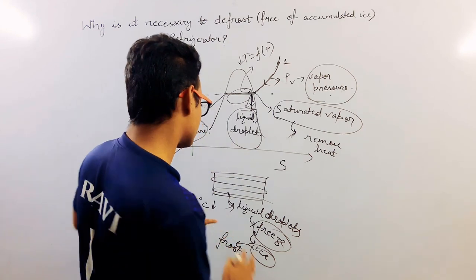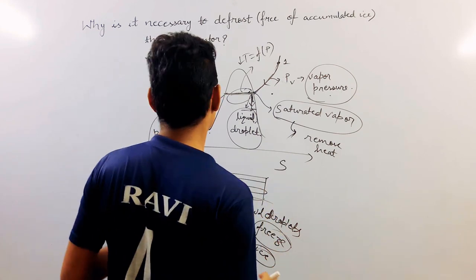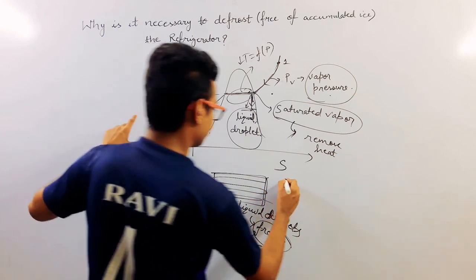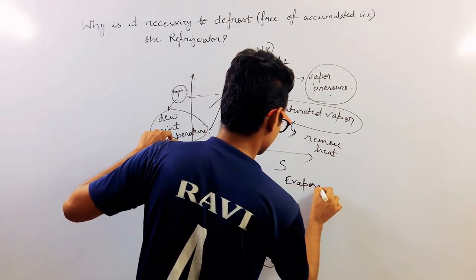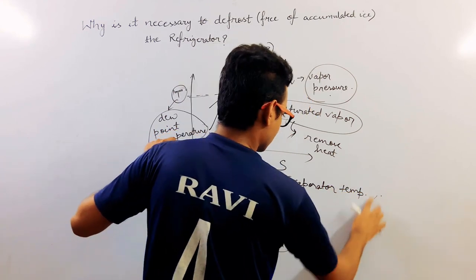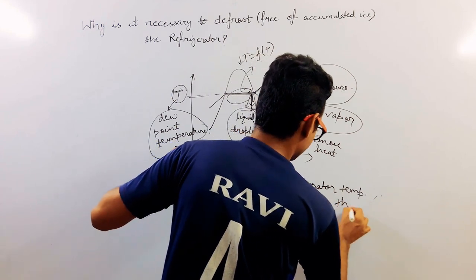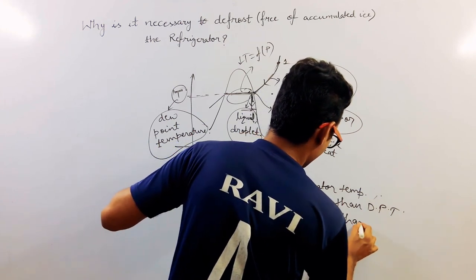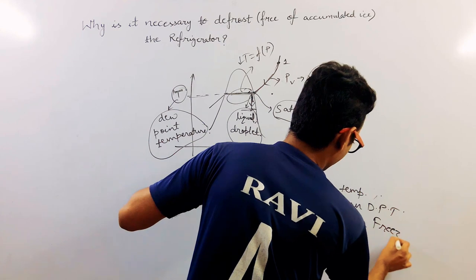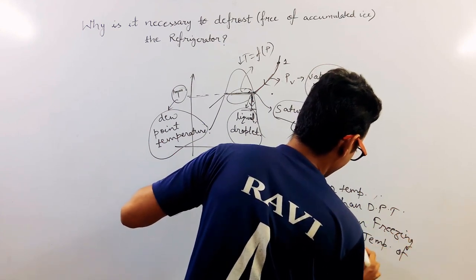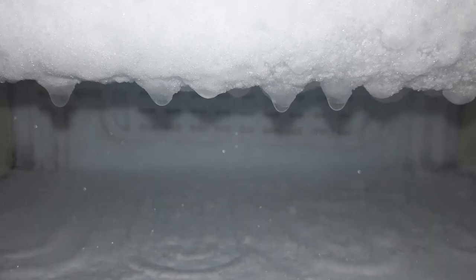So this is how the frost formation happens in case of our household refrigerator. The condition is that the evaporator temperature must be less than the dew point temperature DPT, and it must be less than freezing temperature of water, so that water can freeze and it will form ice. And that is what is manifested in terms of frost formation in case of refrigerator.